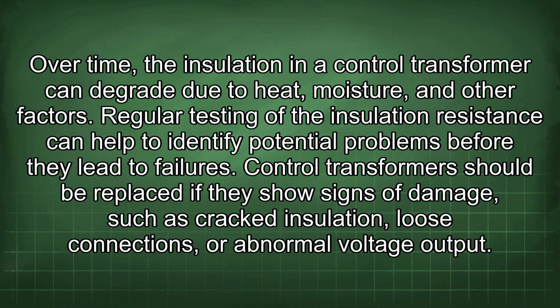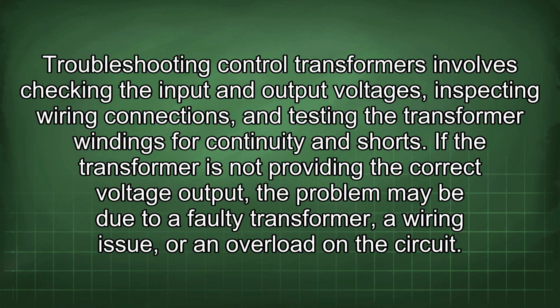Over time, the insulation in a control transformer can degrade due to heat, moisture, and other factors. Regular testing of the insulation resistance can help to identify potential problems before they lead to failures. Control transformers should be replaced if they show signs of damage, such as cracked insulation, loose connections, or abnormal voltage output.